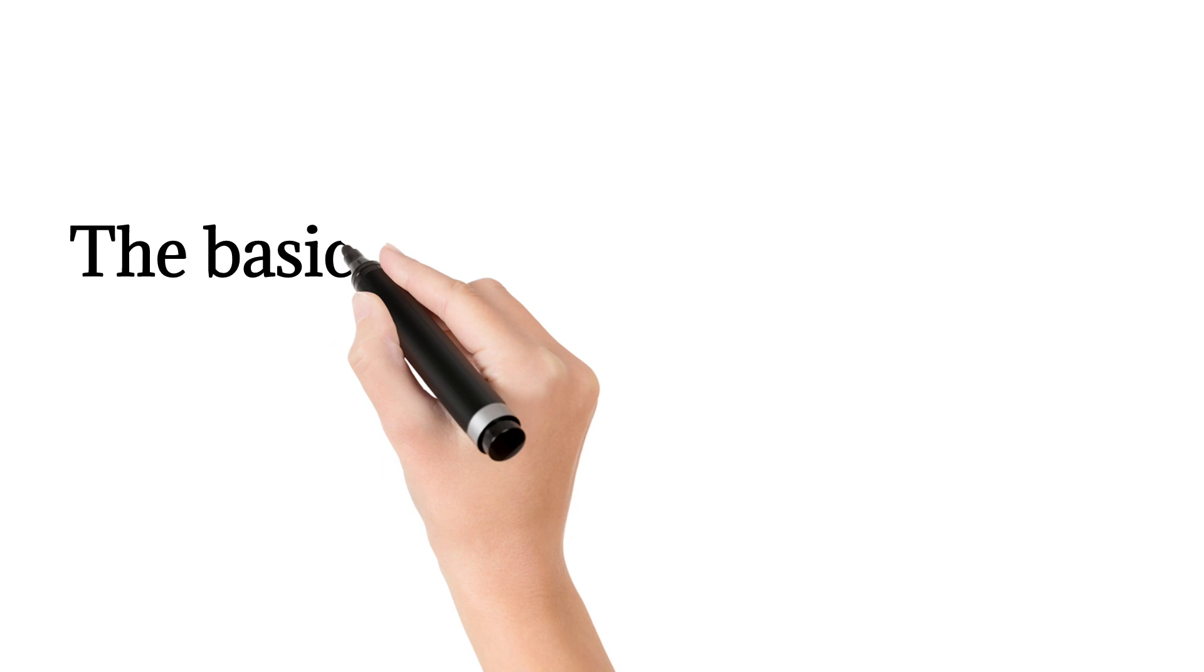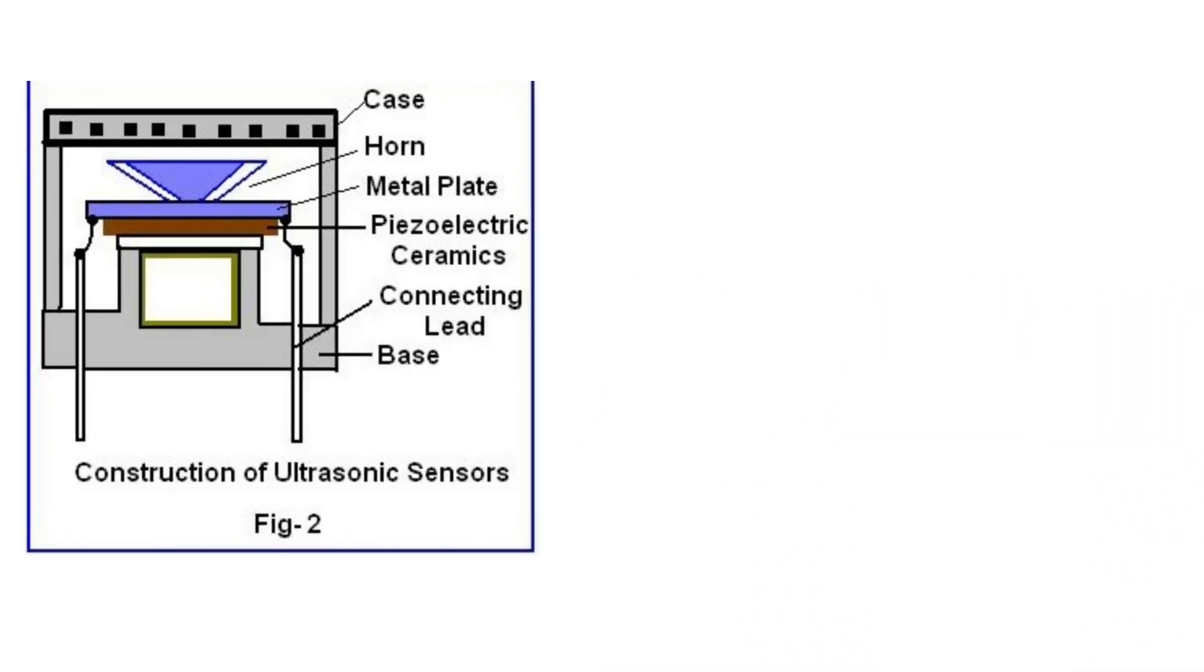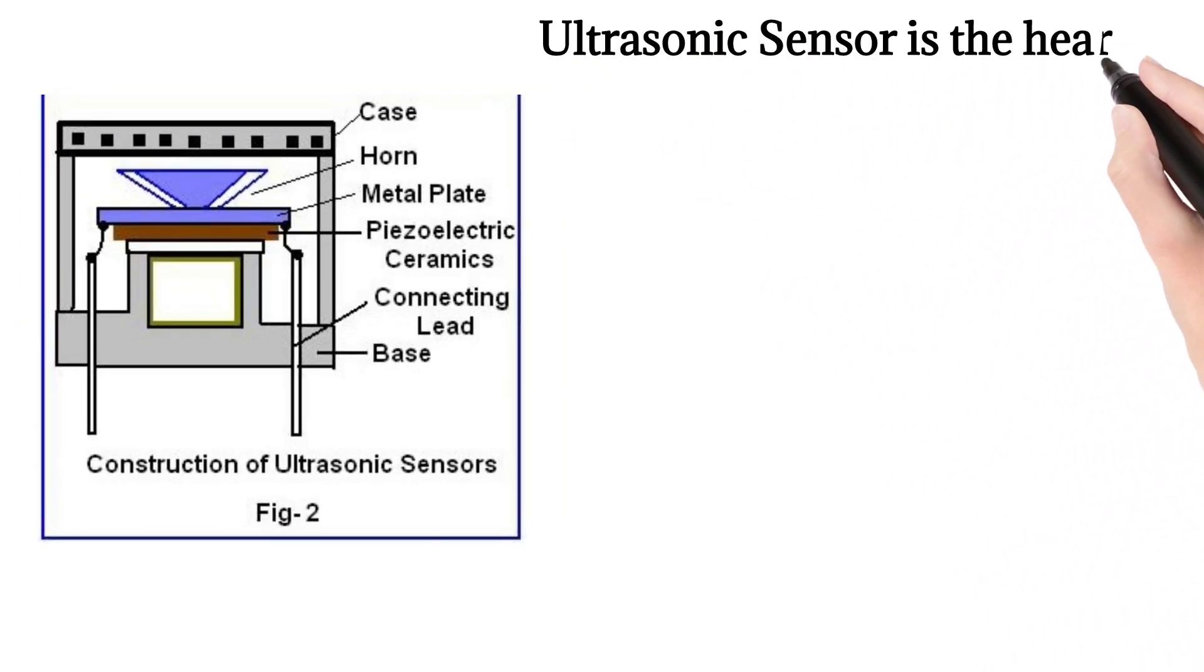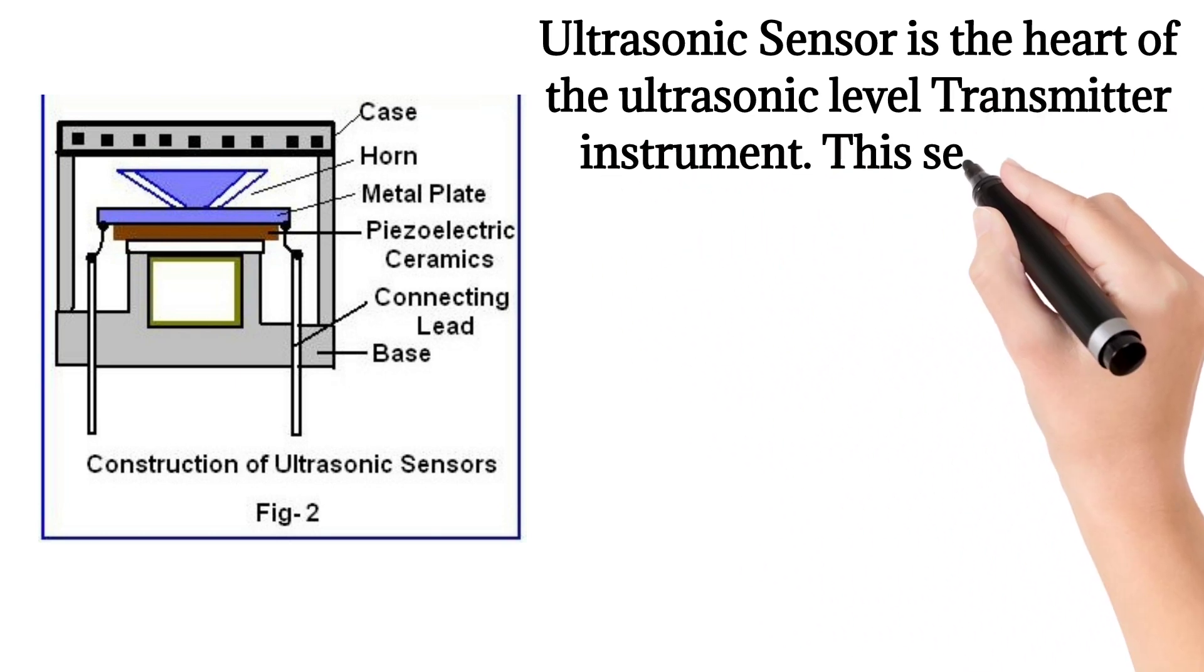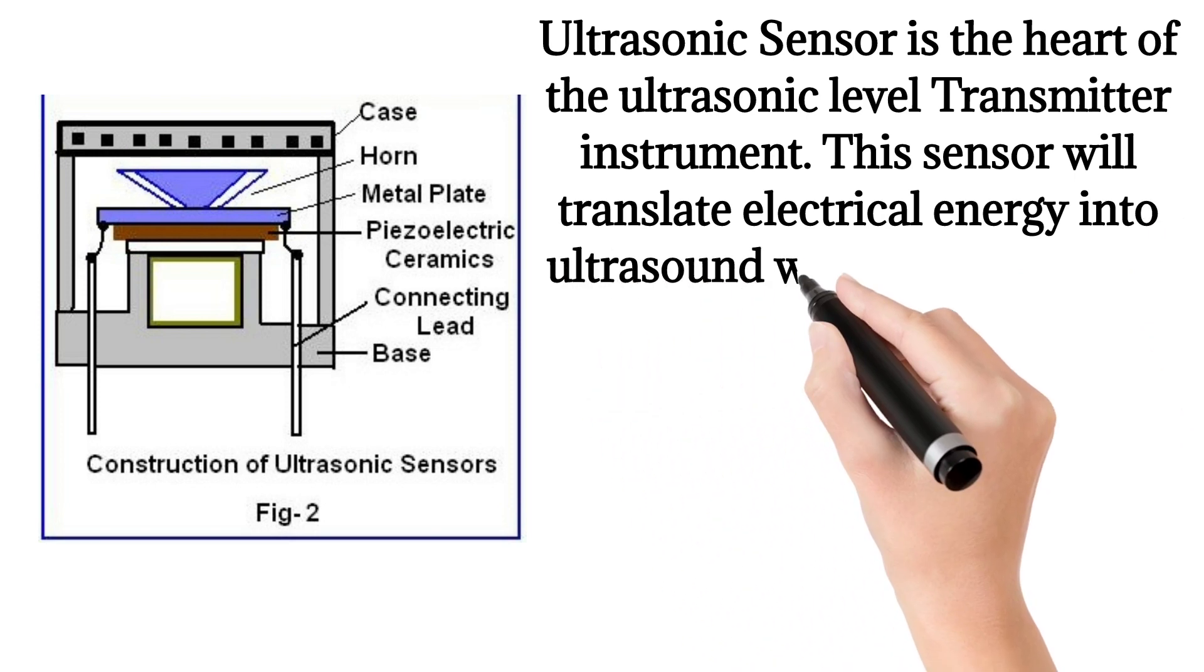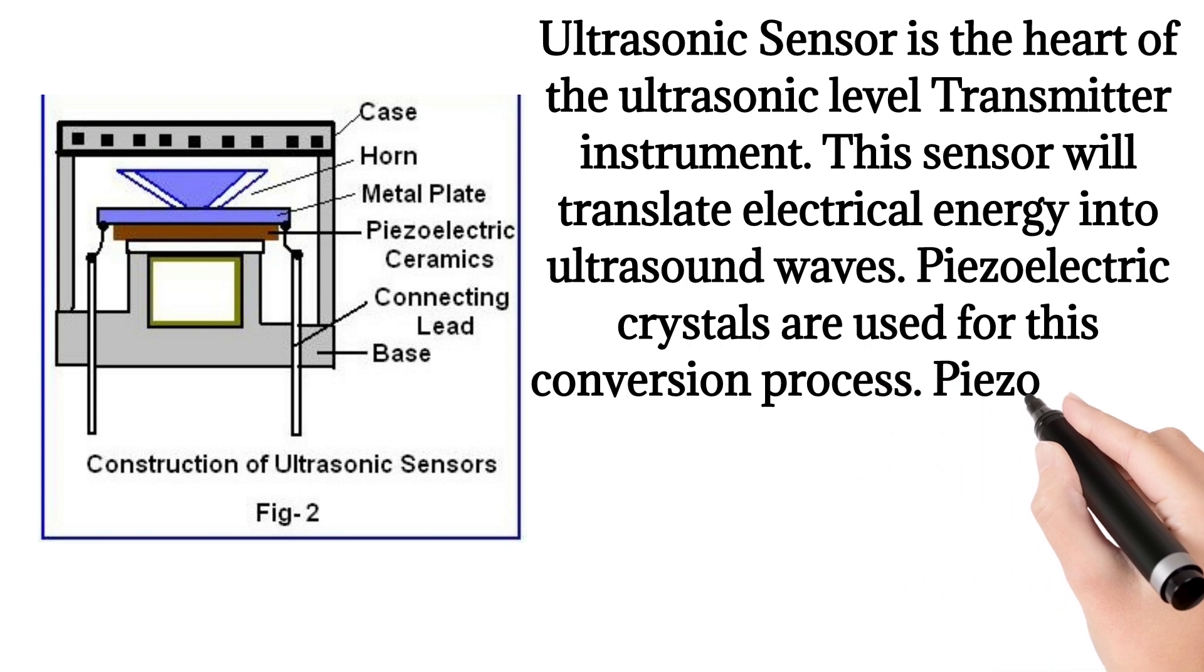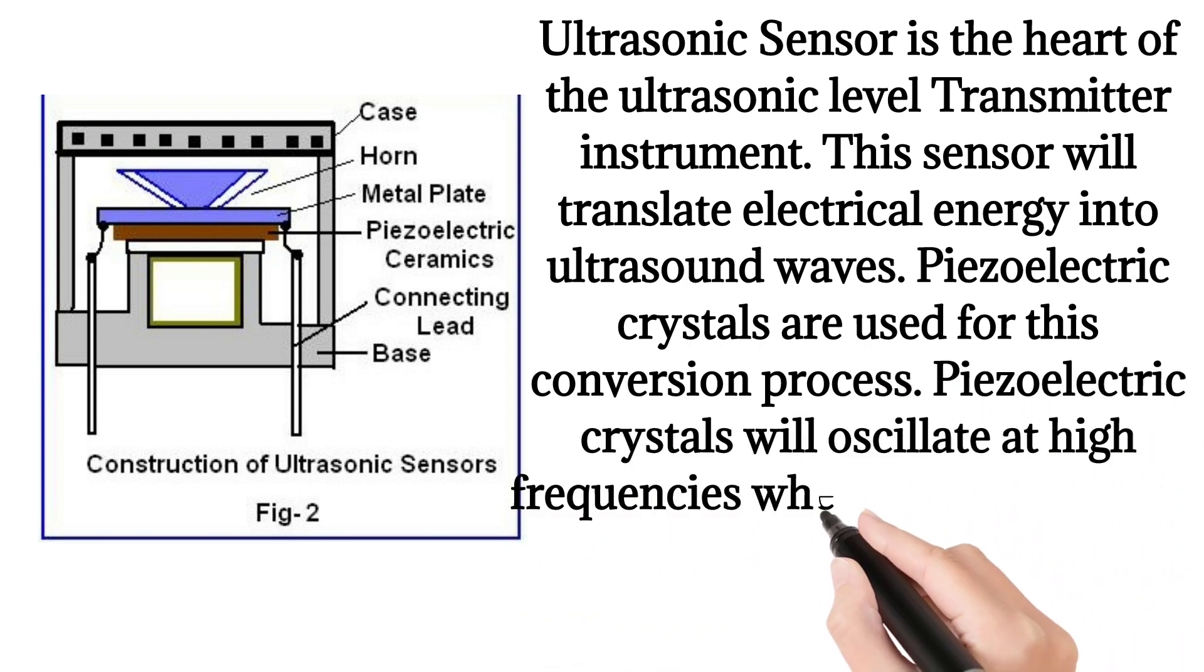The basic structure of an ultrasonic transducer: Ultrasonic sensor is the heart of the ultrasonic level transmitter instrument. This sensor will translate electrical energy into ultrasound waves. Piezoelectric crystals are used for this conversion process. Piezoelectric crystals will oscillate at high frequencies when electric energy is applied to them. The reverse is also true.